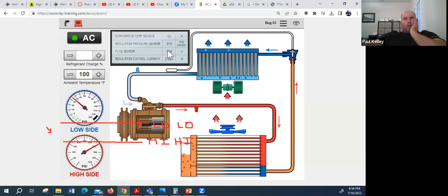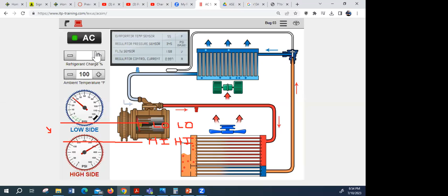The reason I'm going to change it, I have the answer key, and as I recall, I think it's the condenser fan according to the answer key. But I have a very interesting point: if the evaporator temperature sensor says 55, then why is this reading 40? So put it the other way, if this is reading 40, why the heck is the temperature sensor reading 55?